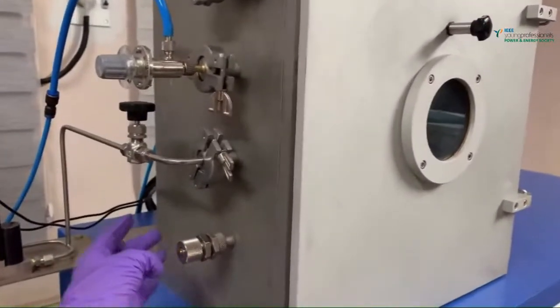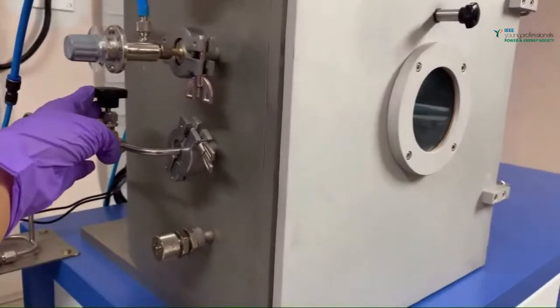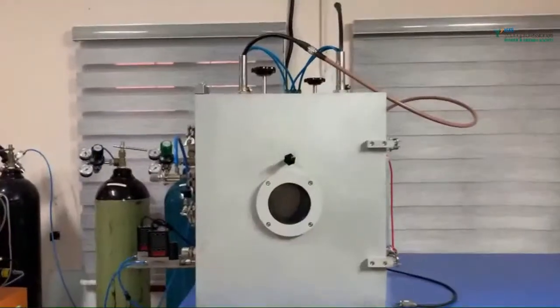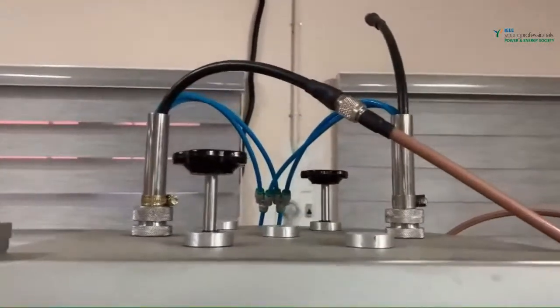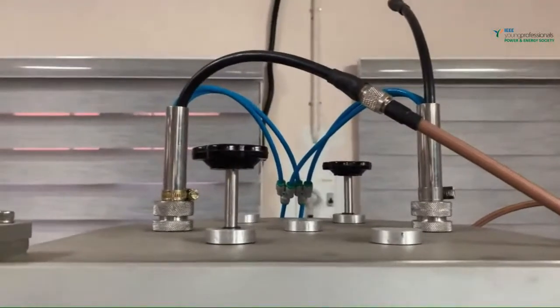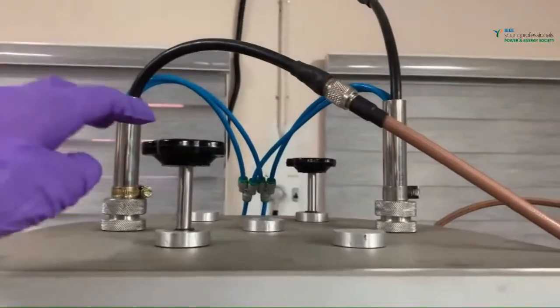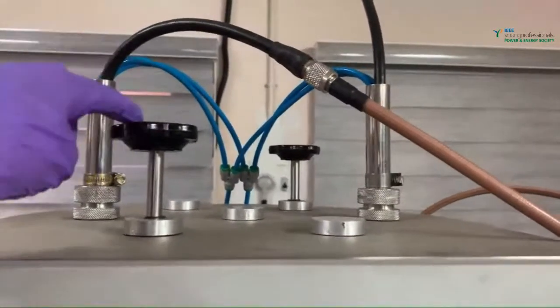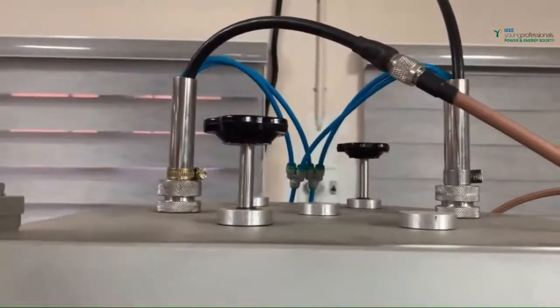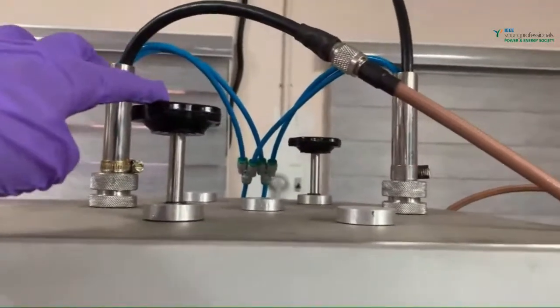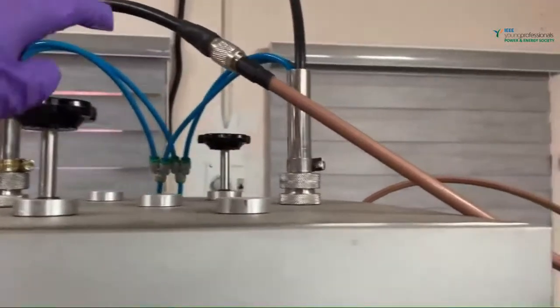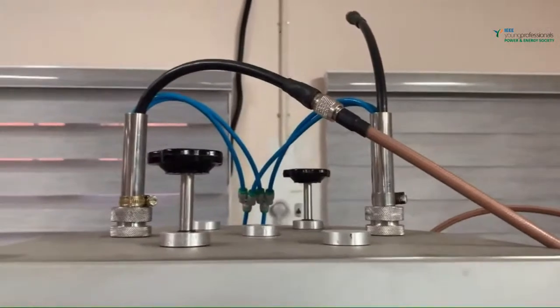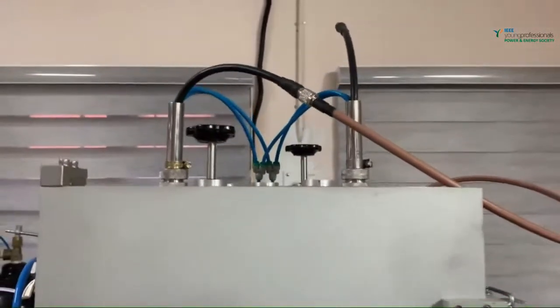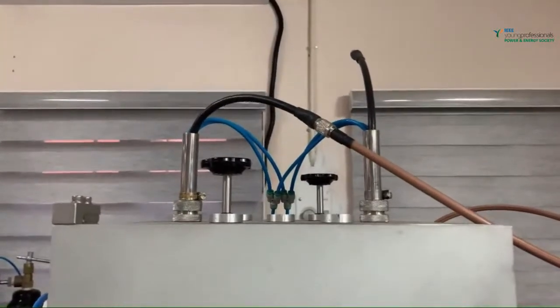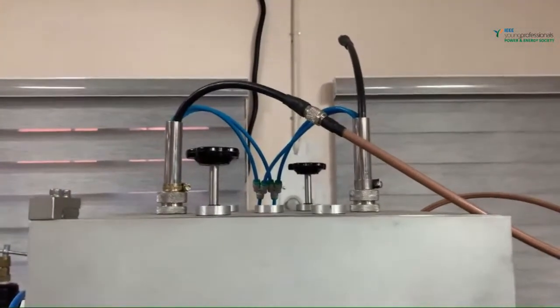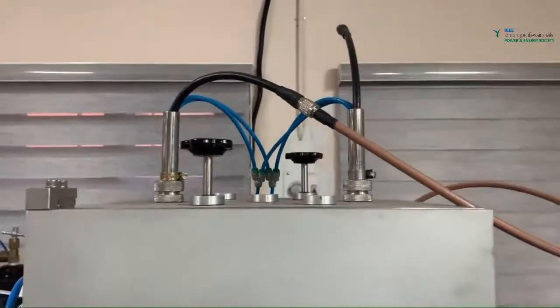This is the air vent valve, and this is the valve to control the gas inlet. Here on top of the chamber, you have certain nodes and some connectors. This is a two target system, so you have these round nodes, two nodes, one at the back side, for shielding the targets. This is for the first target, and that's for the second target. This connector is used for providing power to the system. Either RF power or DC power can be provided. This brown cable is used for RF power, and another black cable is there for DC power.